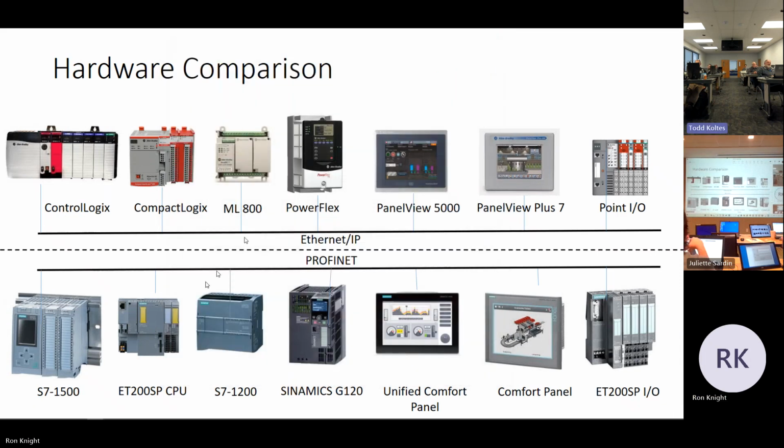And you can't do safety there. They can't do remote I/O. You have onboard IO, and then you've got expansion IO, and it's really based on the model of the 800 that you buy on how much expansion IO you can do. On the 1200 side, and it's not even a fair comparison, the 1200 is a much more powerful processor than the 800. Very similar price point, which is interesting, but a lot more capability on the 1200 side.